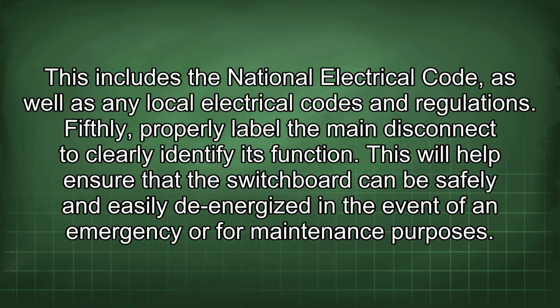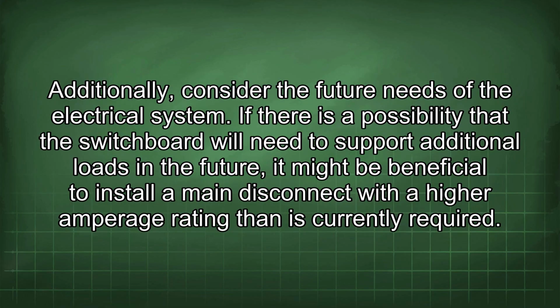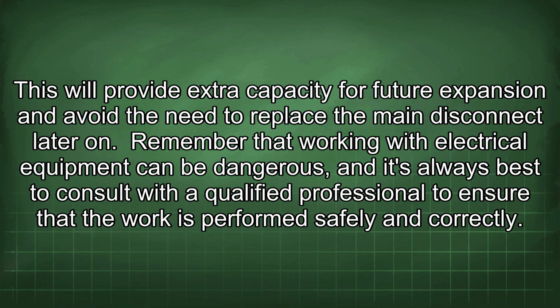Fifthly, properly label the main disconnect to clearly identify its function. This will help ensure that the switchboard can be safely and easily de-energized in the event of an emergency or for maintenance purposes. Additionally, consider the future needs of the electrical system. If there is a possibility that the switchboard will need to support additional loads in the future, it might be beneficial to install a main disconnect with a higher amperage rating than is currently required. This will provide extra capacity for future expansion and avoid the need to replace the main disconnect later on.